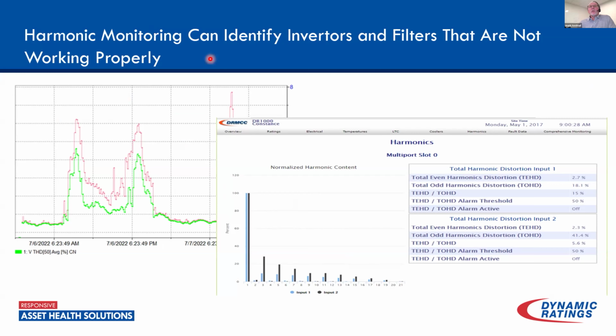With our harmonic monitoring, we can identify not only whether there is a problem with the inverters, are they responding correctly, are all three phases responding the same as we see system events, but also, if there are filters present on the system, are the filters actually working? So again, it's going to provide us information that maybe something has gone awry with the harmonic filtering that's in place, or even in the inverter itself. Again, it's just good information.